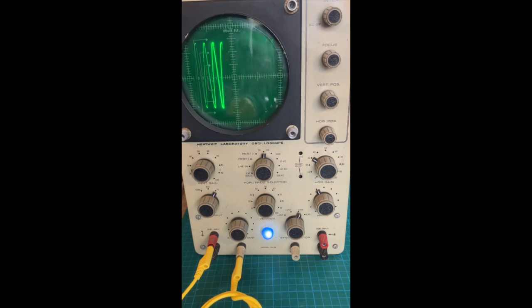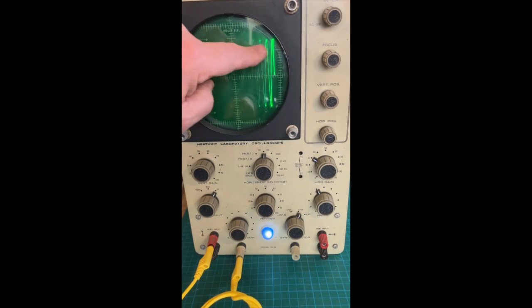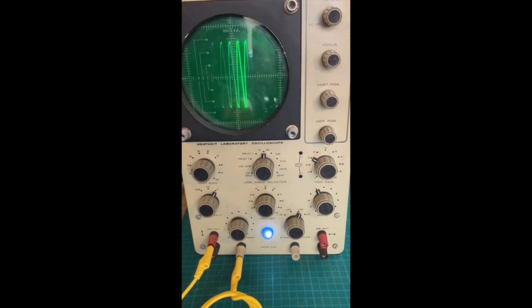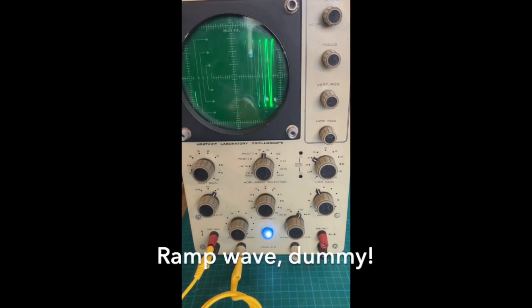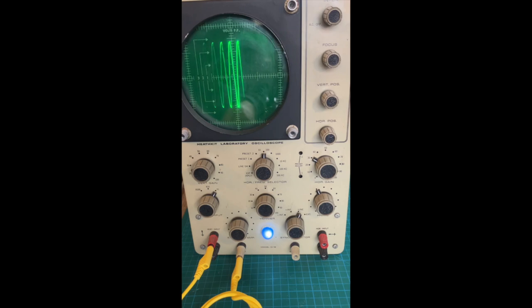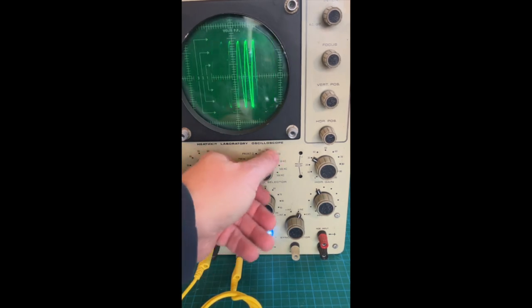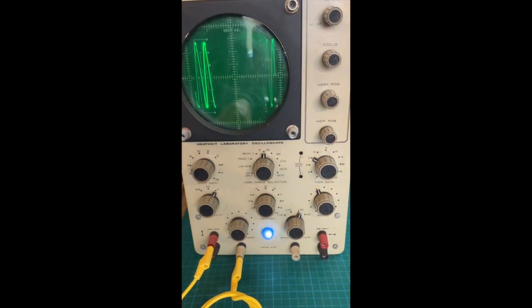But the reason I have it displaying this way is because there's a slight non-linearity in the sweep. If you notice, from here to here, the cycles are a little bit closer together than they are here. So the sweep is not a perfect triangle wave. In the past, I found that this can usually be rectified by replacing the one capacitor which selects that particular frequency when you adjust the sweep frequency. Now there's a capacitor for each one of these settings, and the lowest one in this case I think is a 0.2 paper capacitor, and I think replacing that will make that nice and linear again.